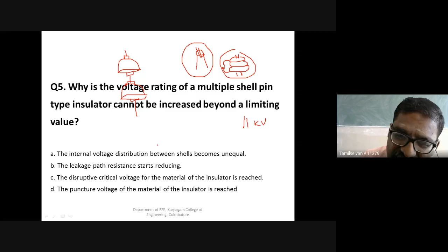That's why we cannot use the pin type insulator beyond certain voltages. Maximum we can use it for 11 kilovolts, or in worst cases, this multi-shell pin we can use up to 22 kilovolts. Beyond that we cannot use it. So this pin type we can use up to a maximum of 11 kilovolts, and this multi-shell pin type we can use for 11. Sometimes rarely we use 22, but it cannot withstand well, there will be frequent punctures. That is due to the internal voltage distribution between the cells becoming unequal.